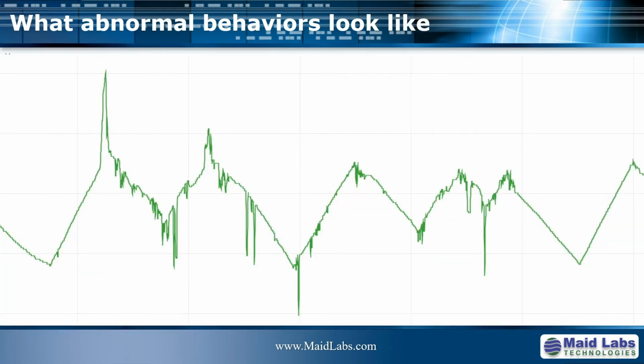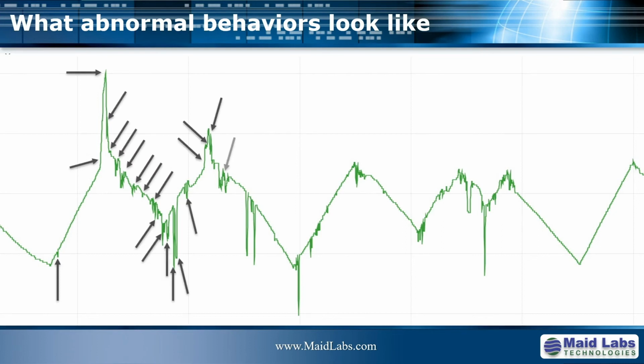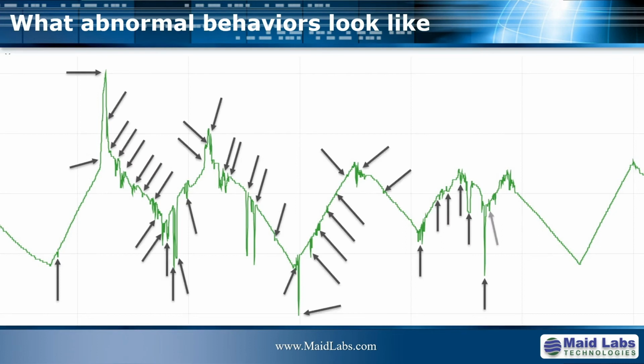When you have a defective level sensor, it looks something like this. This came straight out of a lift station with a SCADA system, a top-notch SCADA system, that didn't discover anything abnormal in that lift station, by the way. Even if all the pumps were starting together at the same time, like every 8 seconds for hours in a row, it was not enough to create an alarm.